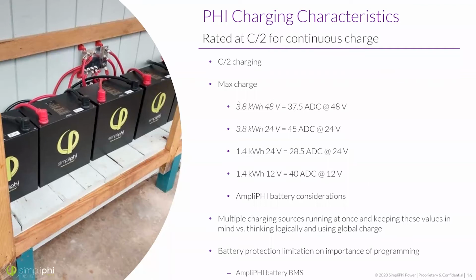So C/2 for a 3.8 is 1.9 kilowatts. If we were to talk in kilowatts, and then you just convert from there. So I would do 51.2 as the nominal capacity of the battery. So that would give you this value here. I think it's actually even a little bit off. I believe they are using 52.1. Yeah. So just note, this is just converted from kilowatts at C/2 into amps DC.